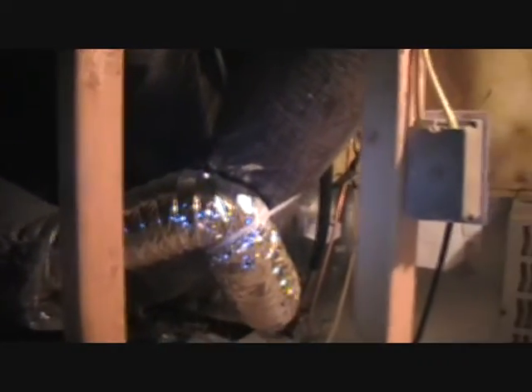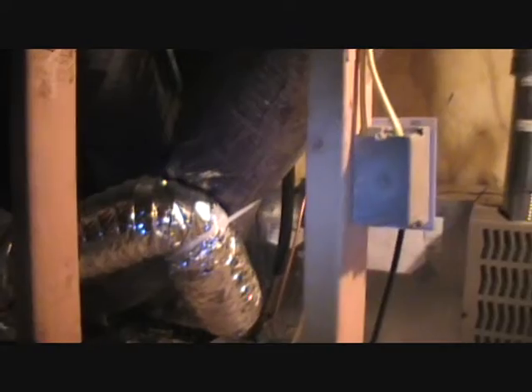As you can see, the flex runs run all over the place and just dart in and out. And keep in mind, this is the finished product. How this passed inspection, I'm really not sure. Probably a product of the housing boom we experienced here in the last 5 years. I'm sure that you can see right here that they actually only ran about 2 feet of trunk line from the coil where they tapped in with flex runs.